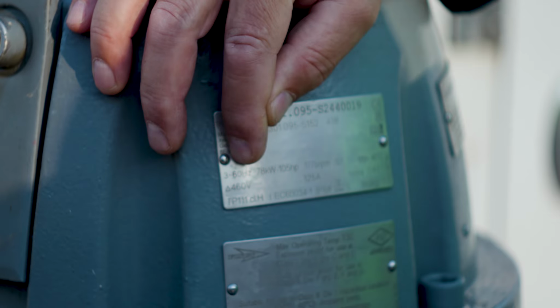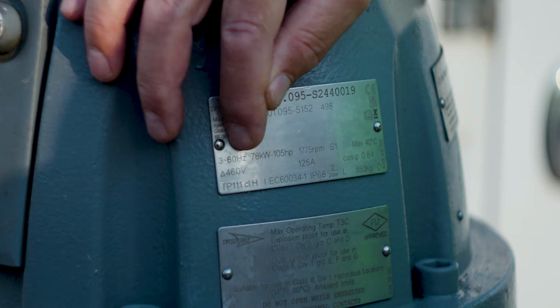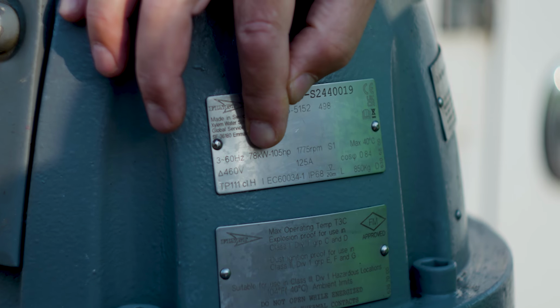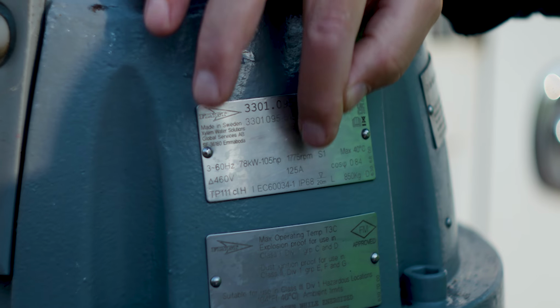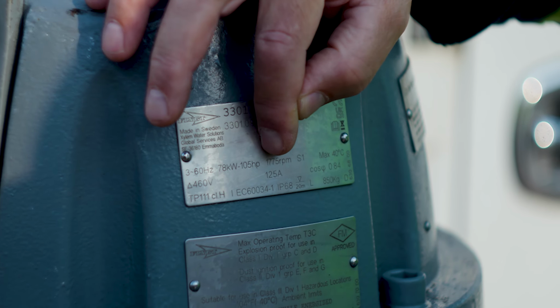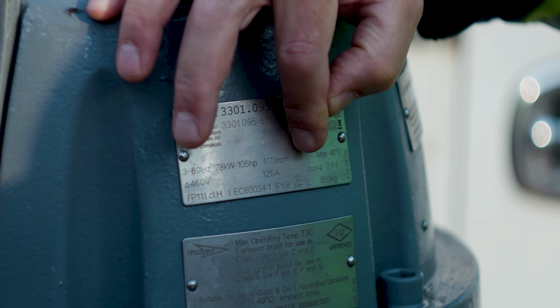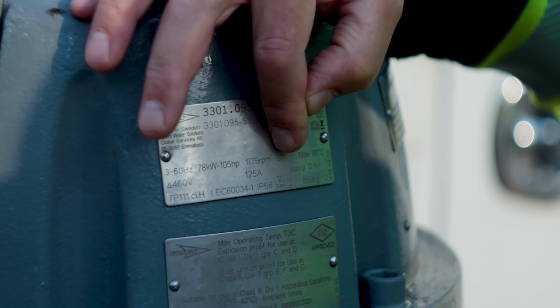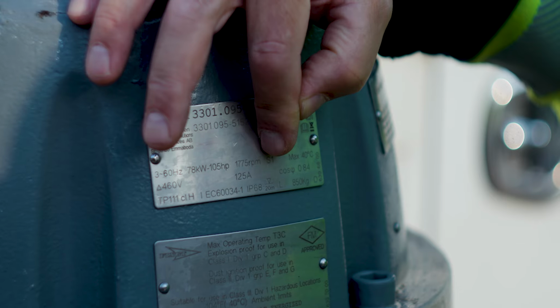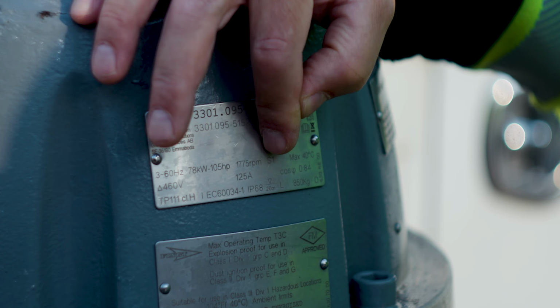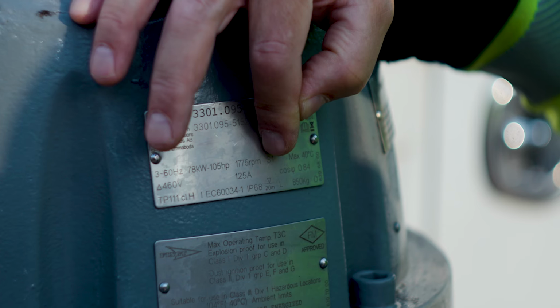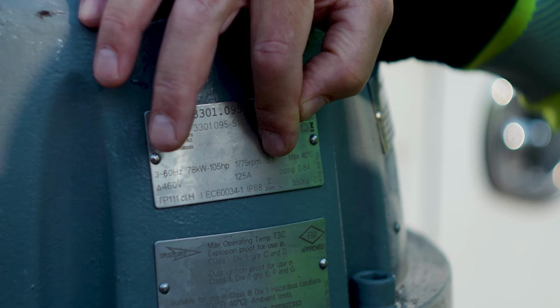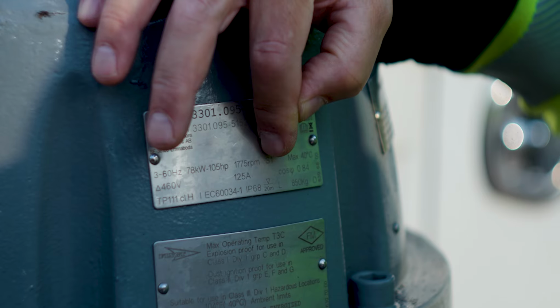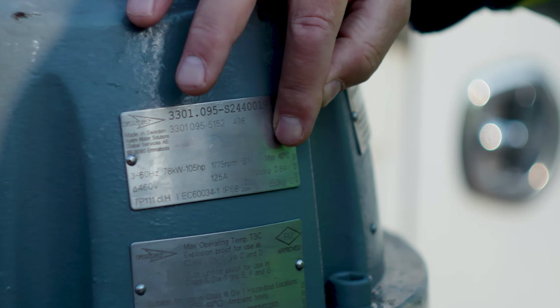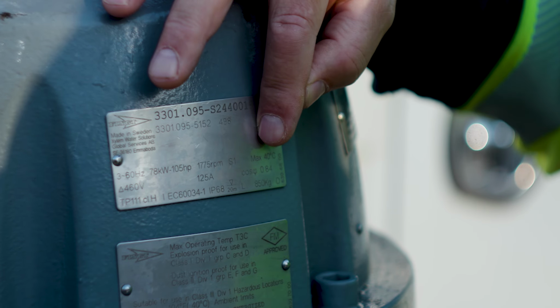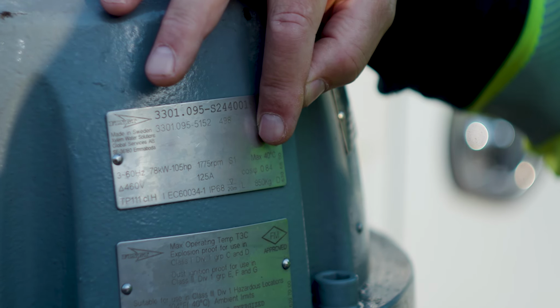There's the three-phase 60 hertz telling you what type of motor it is. It's 78 kilowatt or 105 horsepower. The speed of the motor at 60 hertz is 1775 RPM, and it has an S1 duty rating, which means that it's made to operate at full load amps, but not more. And the reason it's S1 is because it's a VFD inverter motor. You still have the combined service factor of 1.15, including the pump and the application. The motor temperature rating is 40 degrees centigrade, which means it can operate in ambient temperatures up to 104 degrees.